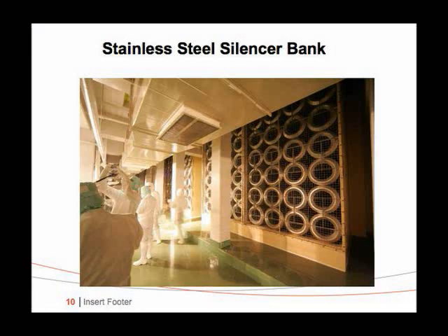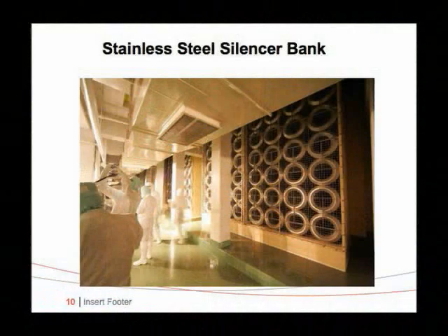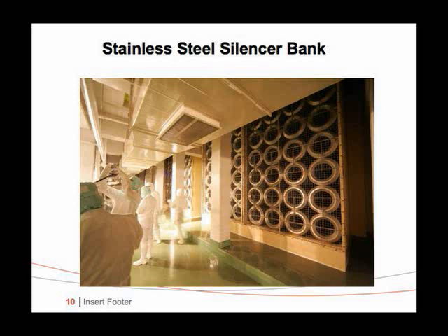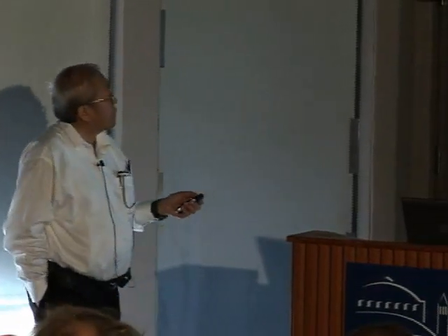Another industry, this is the semiconductor industry, wafer fab in Japan. This is one of five on the same site. And I'm told the government ministry came and said, let's upgrade the fab for better efficiency. So these are stainless steel silencers. Maybe you've seen it. It's very common in Japan. And on the other side of the stainless steel wall of silencers, you can see the anchor points for the old axial fans, which were upgraded at government expense into these mixed flow fans. So you would expect an upgrade to deliver substantially better performance. I think cost is not an issue. It's a kind of a test project.